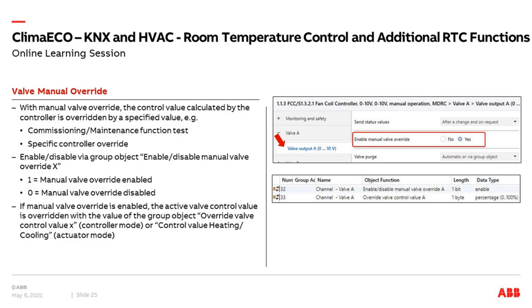Manual overwrite of the valve is a further simple parameter. You adjust it at the valve output and get a one-byte group object available to position the valve to any certain value. There is also an enable/disable object — important so that nobody can overwrite unintentionally. Overwriting may be necessary for commissioning tests or maintenance tests whenever you need a specific valve position independent of normal function.